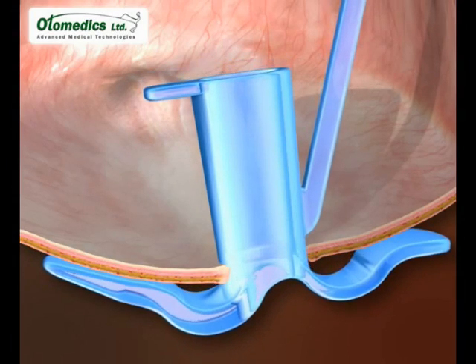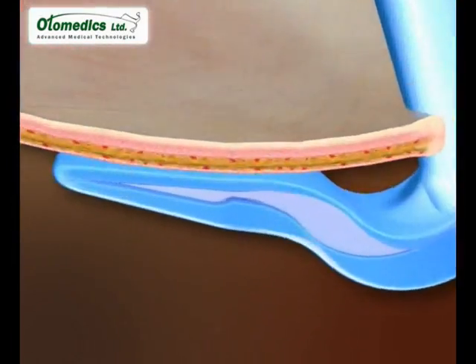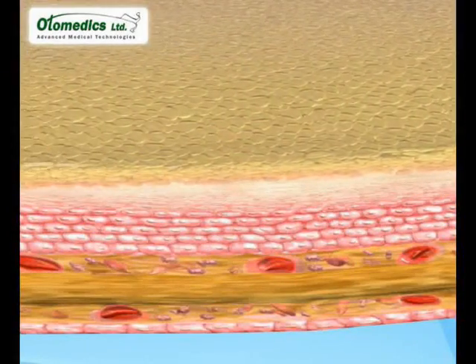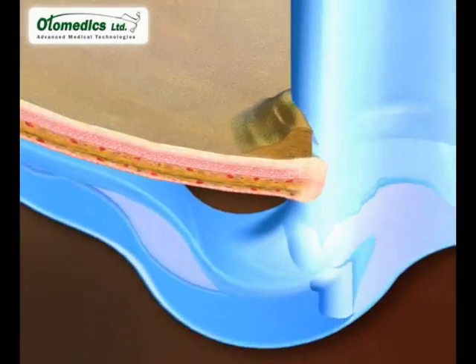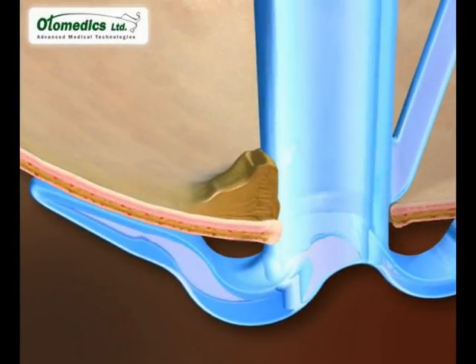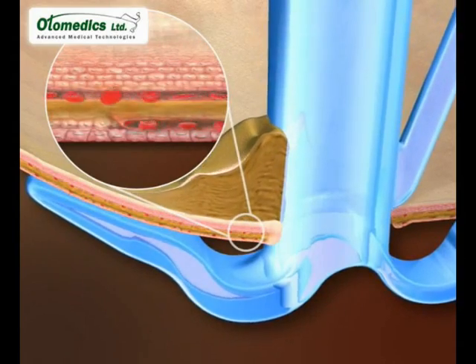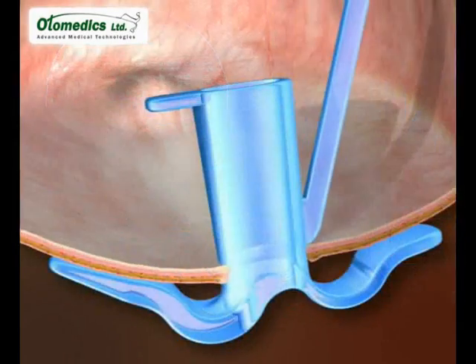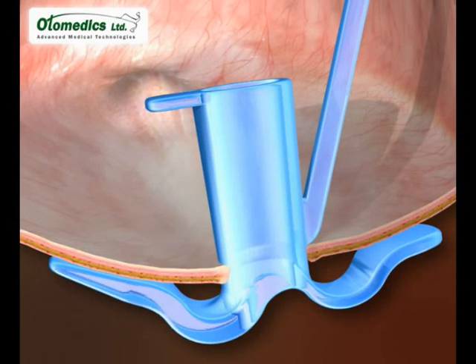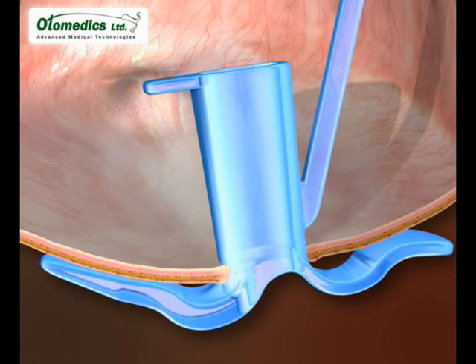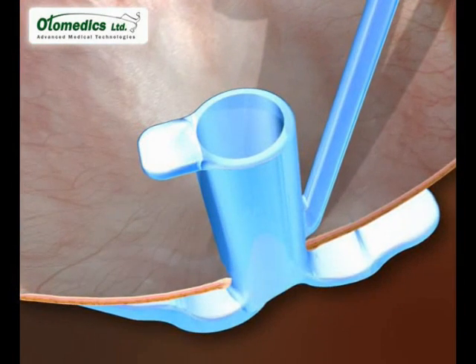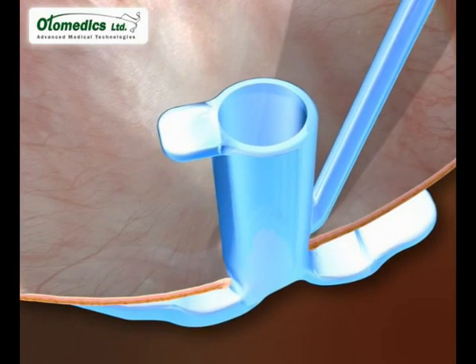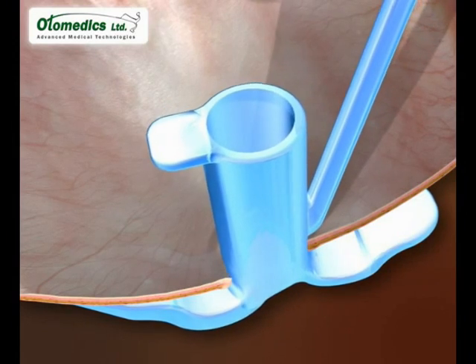The tube has two asymmetrical arms. The thicker arm is designed to resist the pressure of the desquamated epithelium that pushes it posteriorly, anchoring the tube in place while preserving the blood supply to the rim area. The other arm helps keep the tube in place and is weaker. By positioning the extraction handle posteriorly, the surgeon can be sure the tube is positioned in the right direction. The arms tilt upwards to meet the eardrum and divide the pressure equally over the contact area, especially towards their ends.